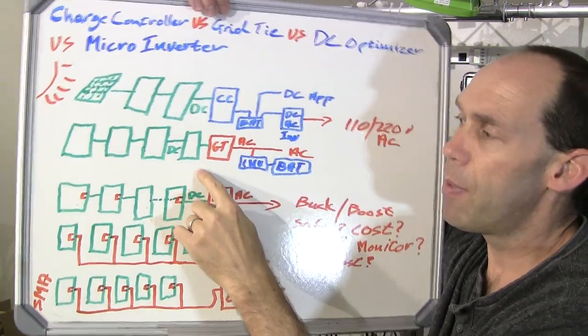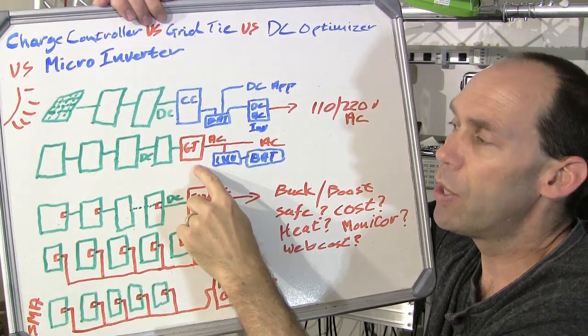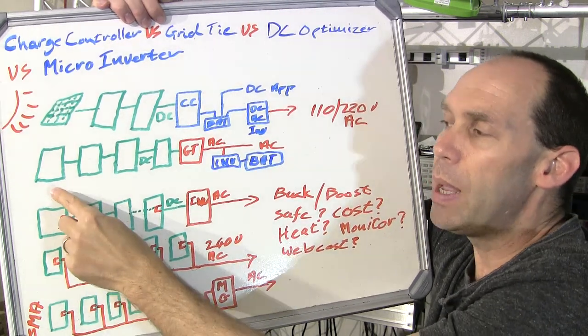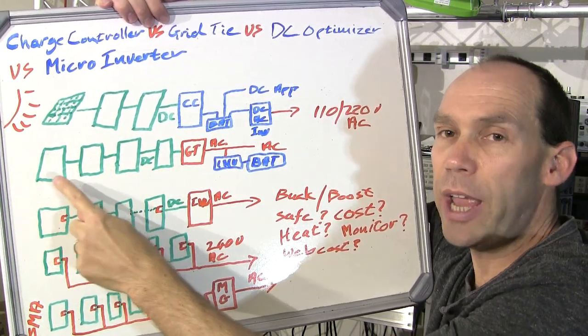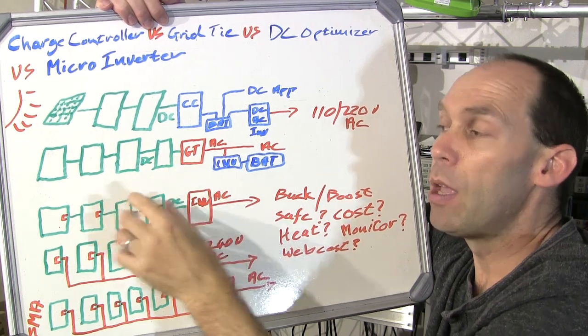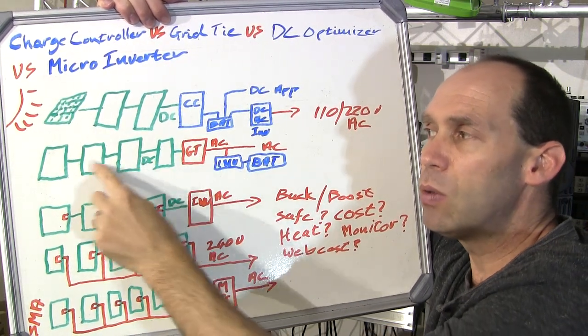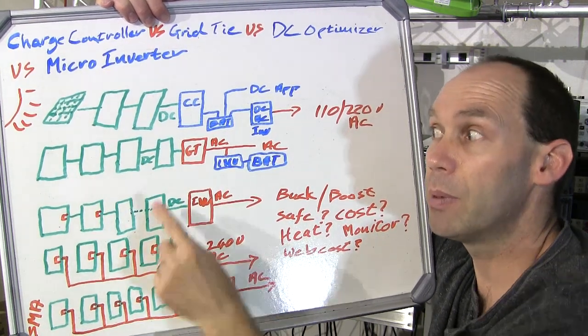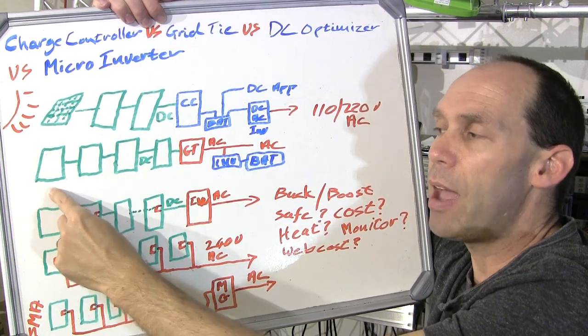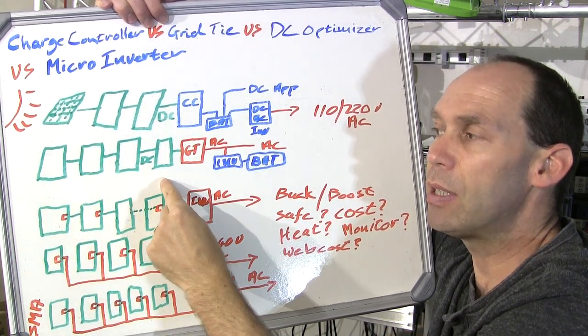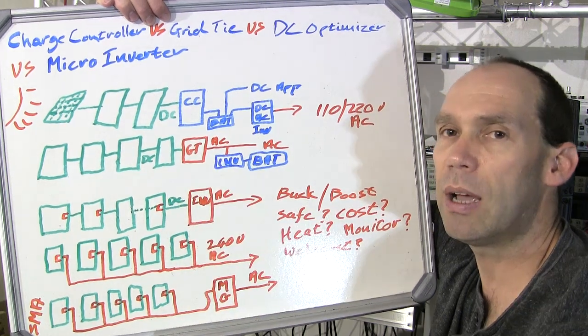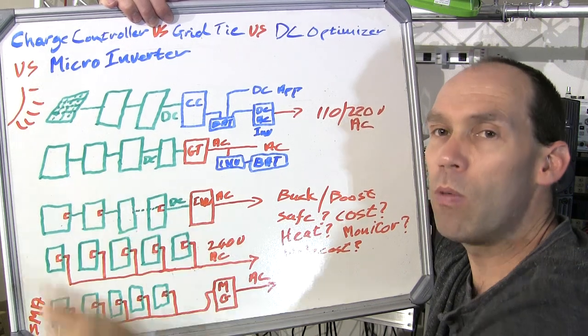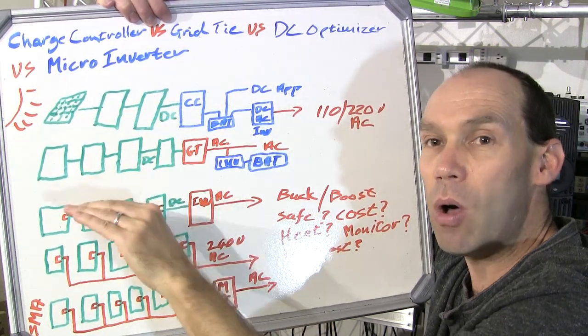Looking at the most common installations these days using grid tie inverters — what are the challenges with this setup? One of the big ones is that you've got a whole lot of solar panels chained together in series. Often you'll have multiple strings, because there's a maximum DC voltage allowed for your grid tie inverter, so you'd have one string in series and a second string also in series, then joined in parallel coming into your grid tie inverter. Now if you have any shading on any one or more of these panels, that potentially brings down the whole string.